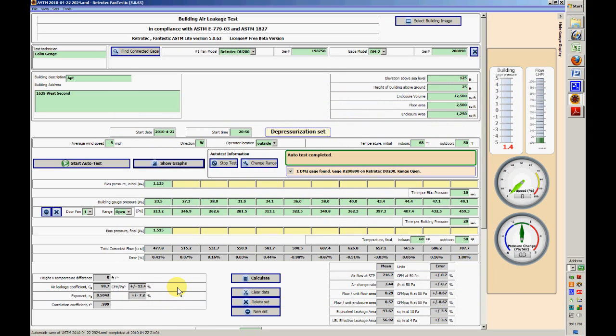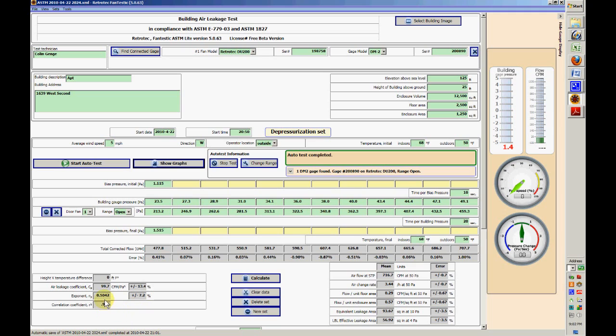So there we have a complete test. All these little boxes have been filled out, and we've got a flow in CFM that's been calculated for each one of these flow pressures that the fan has produced. And it looks like a fairly good test.